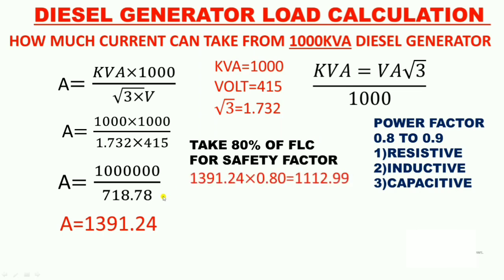If we take 80% of the full load current: 1391 × 0.80 = 1112 ampere, and this is the main answer. So, if an interviewer asks about the full load current of a 1000 kVA diesel generator, you can say the full load current is 1391 ampere, and the current you can safely draw with the safety factor is 1112 ampere.